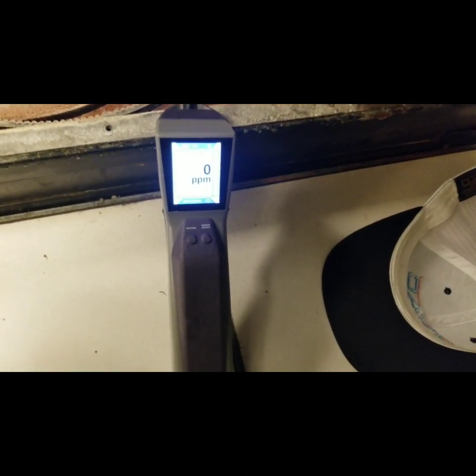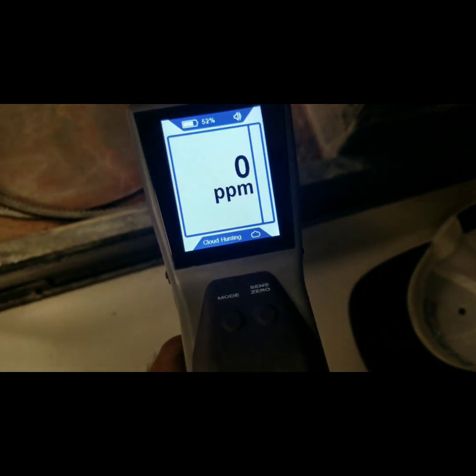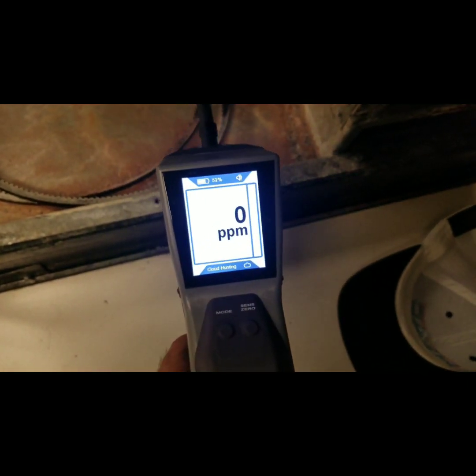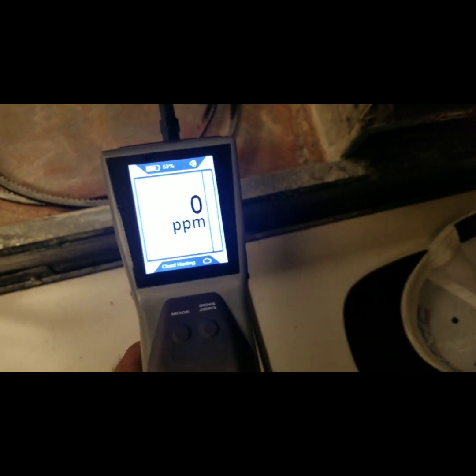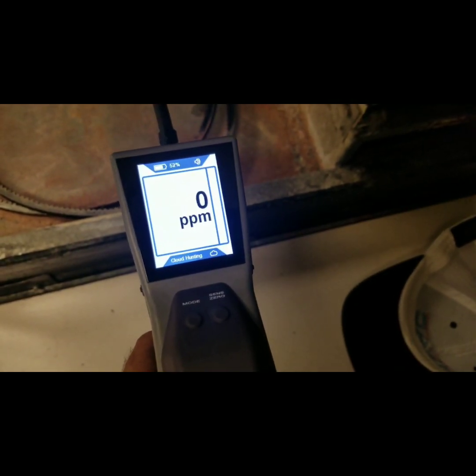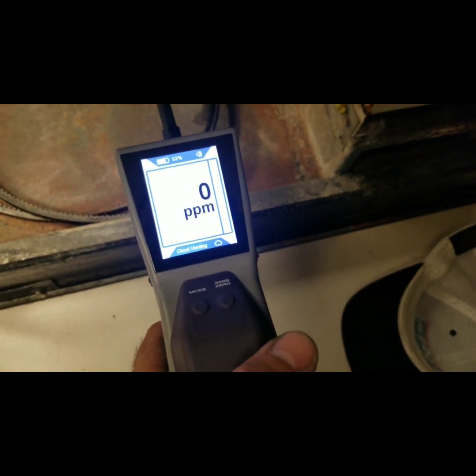I have the D-TEK Stratus in cloud hunting mode, or cloud-based mode. Basically, this is going to find a cloud of refrigerant. It's going to give us the level in ppm, so it will tell us around the area where the leak is, and then we can change the mode to pinpoint the exact location of the leak. Let's try to find this leak in cloud hunting mode.